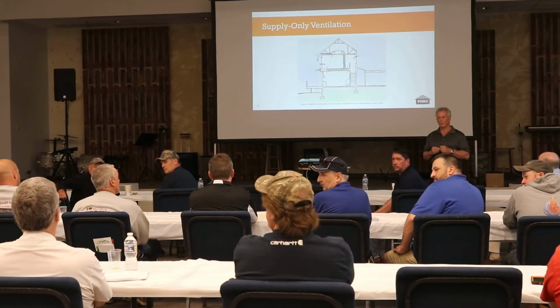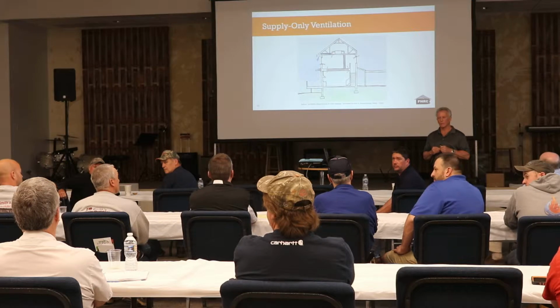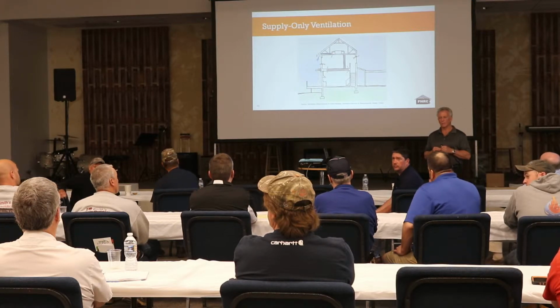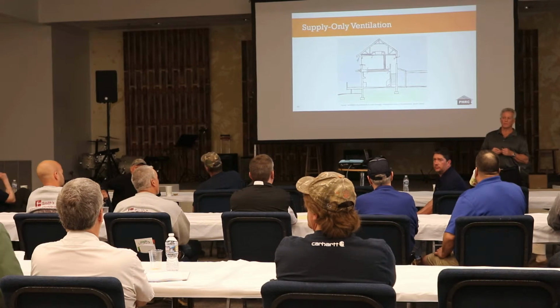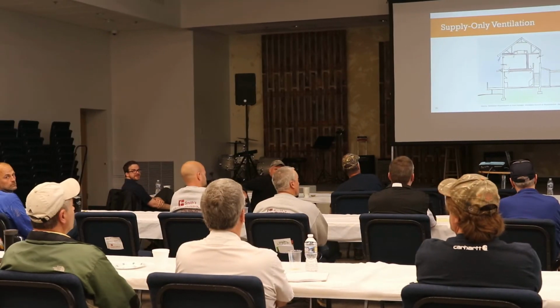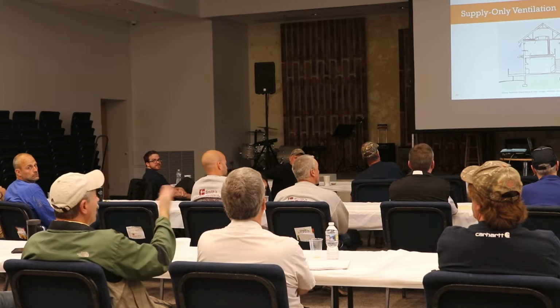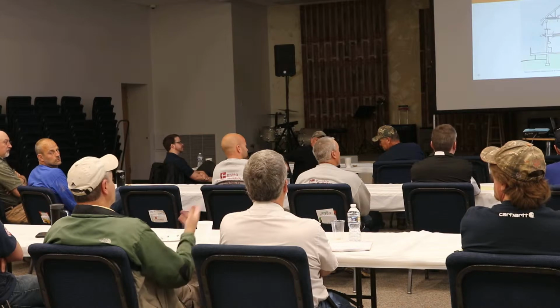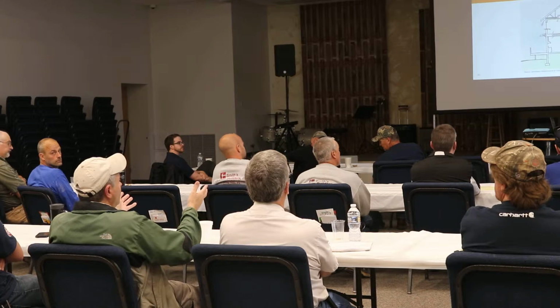I'm not completely sure they're going to get the amount of CFM just drawn in, because there's not that much air leaving the house. But they claim they've been getting outside air drawn into that return with nothing leaving. Right. And they're claiming they're getting it. They actually put a damper in to throttle it back, because I was really surprised. I said, well, there's not that much air leaving if you need 100 CFM or 150 CFM, and they said, no, it's pulling in that much. They're actually putting the damper in to throttle it back, and then the controls to open and close it completely.